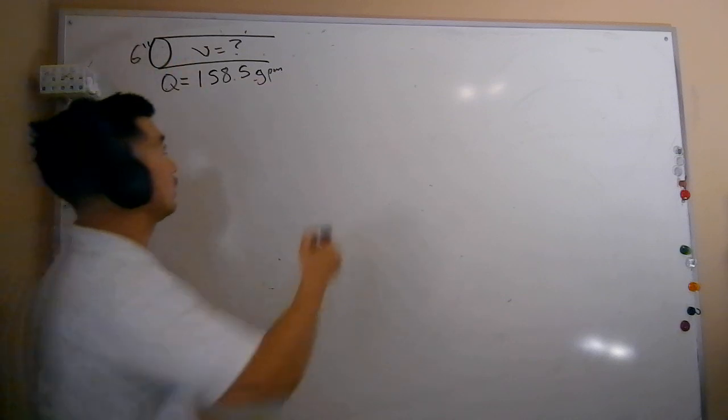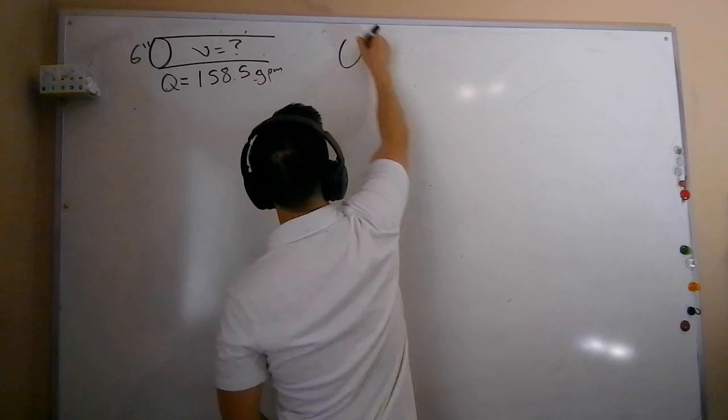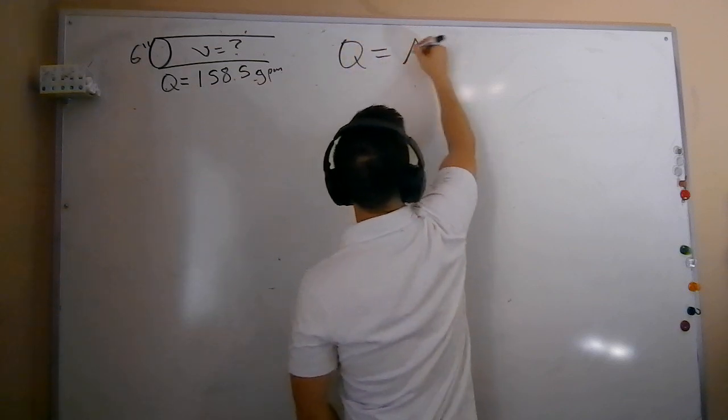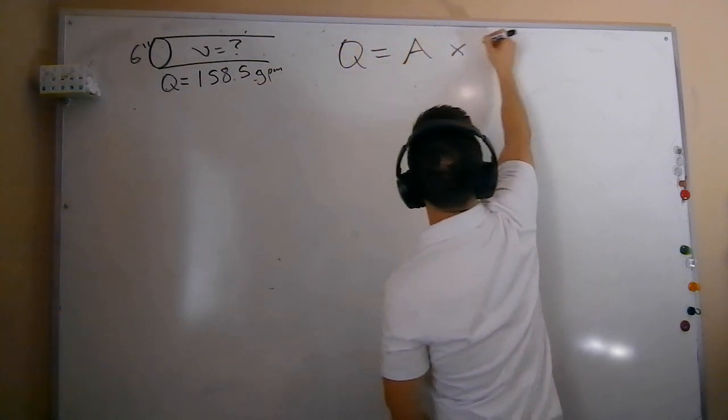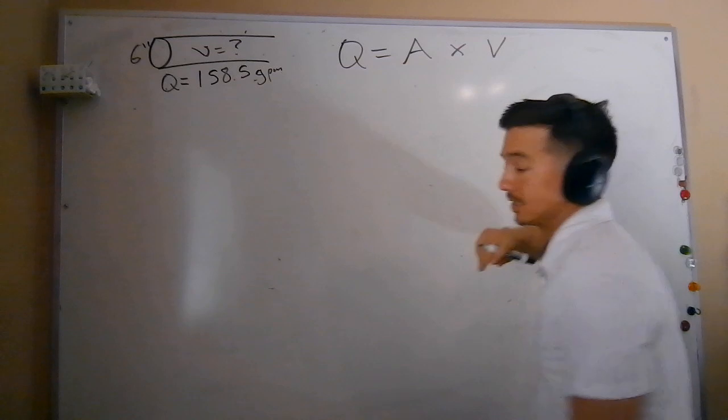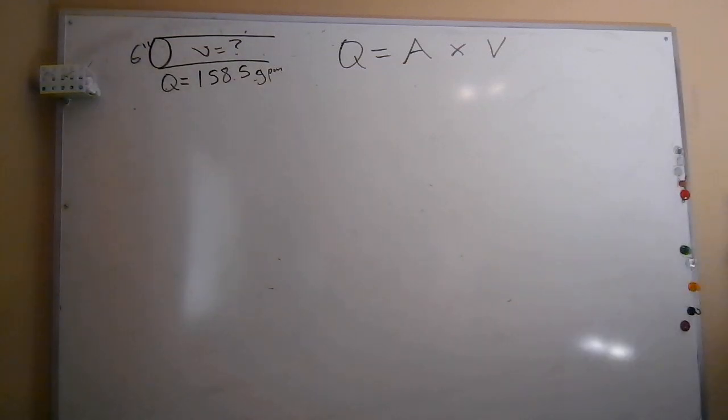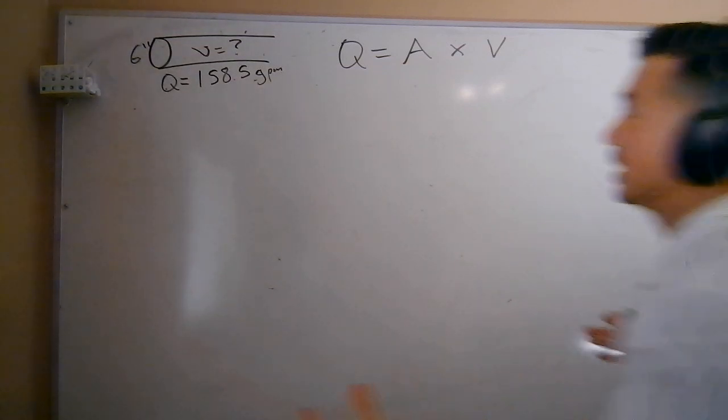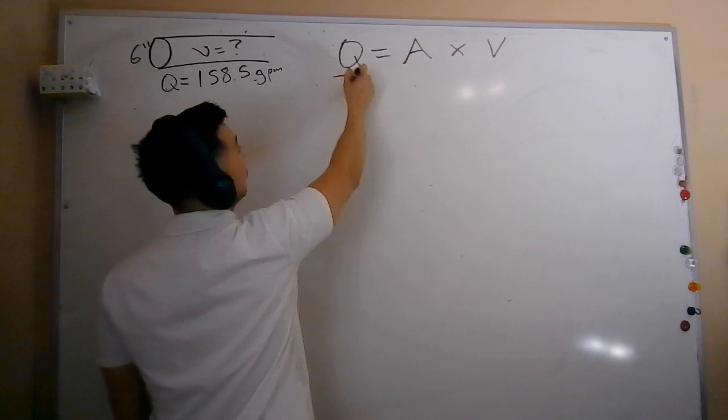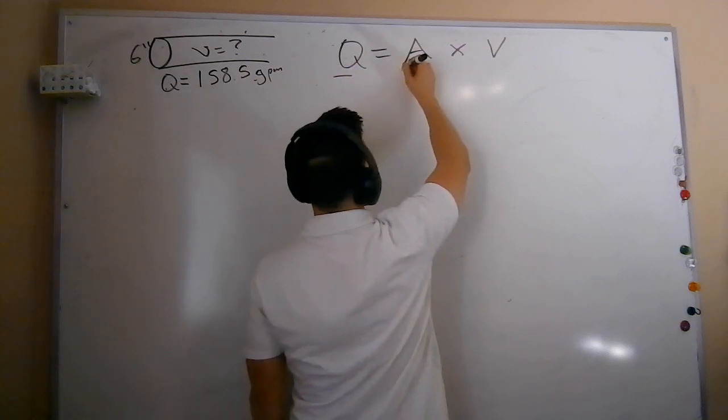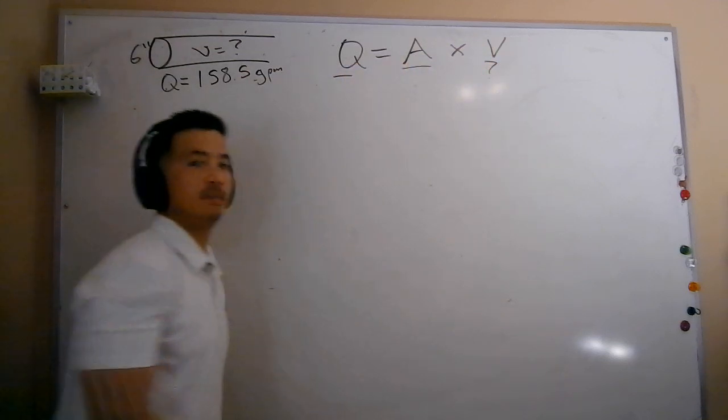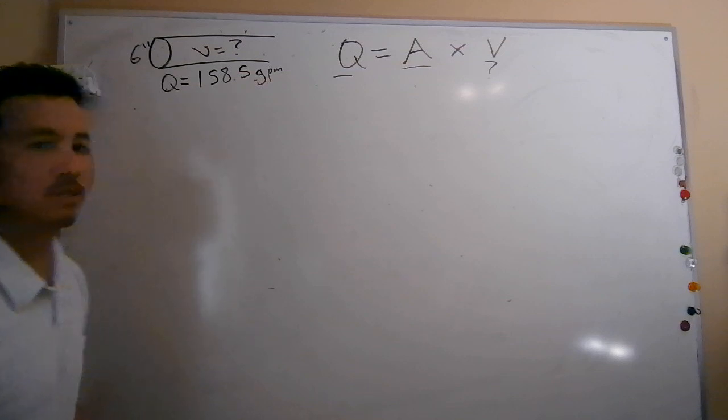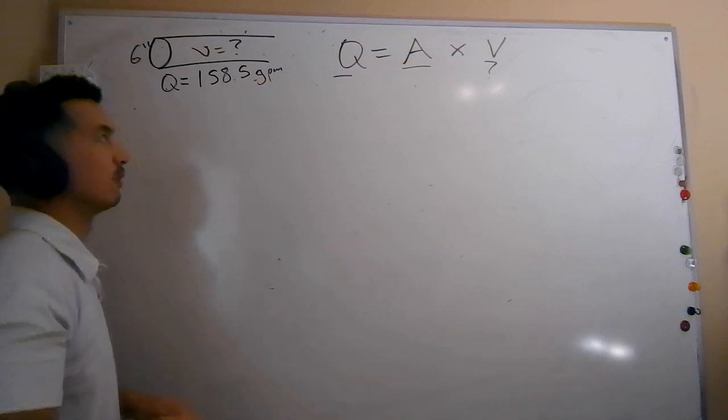So in this example, we can start with our formula for flow, Q equals AV, or area times velocity. So Q, the quantity of water, equals area times velocity. In this example here, we're given Q. We can calculate the area. What we don't know is our velocity. So it's a little bit different from how we sometimes traditionally use the QAV formula.